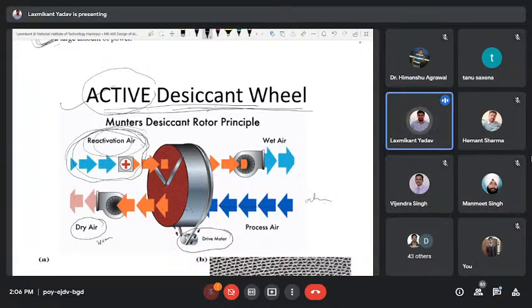And this is the reactivation. So we will heat the atmospheric air. Okay, and due to this we will remove the moisture from the desiccant. In the adsorption section, moisture transfer takes place from the air to desiccant. In the reactivation section, the moisture transfer takes place from desiccant to air. So again, desiccant is ready to adsorb the moisture. And one small motor of around 6 to 10 watt power is used to drive the wheel.